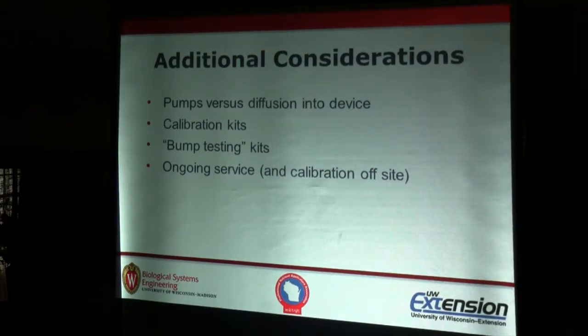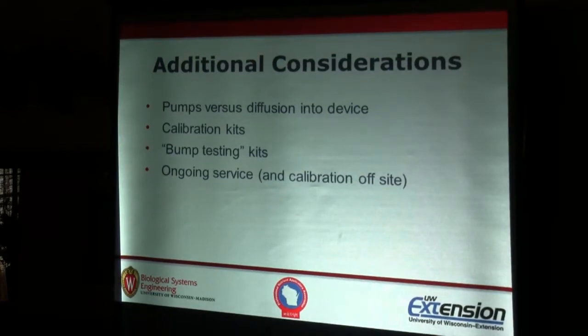I think you asked me if I talk about bump testing. I want to talk a little about calibration and bump testing. Calibration is very important, it's very critical actually. Again, one of the benefits of getting hooked up with a service representative is they can often help provide calibration services and support for a cost. It's also required with many types of monitors that you bump test, not occasionally, but before most uses. OSHA says prior to each use you're supposed to function test the device. So I've got a great definition to help you along with that.